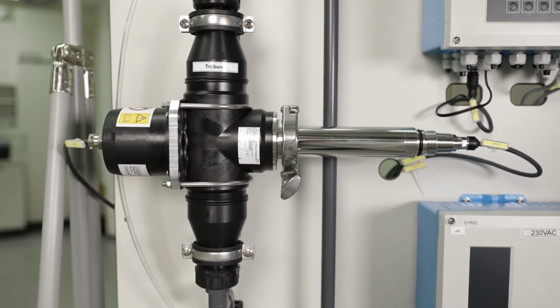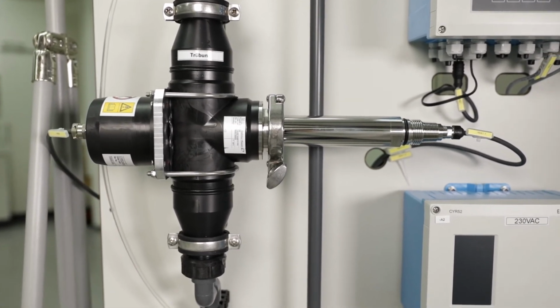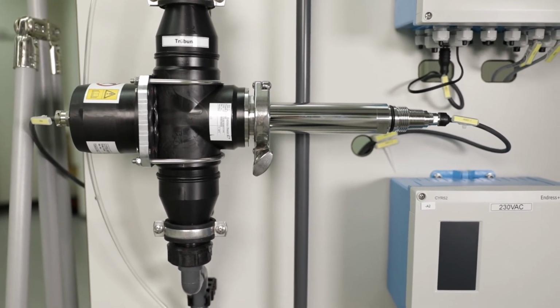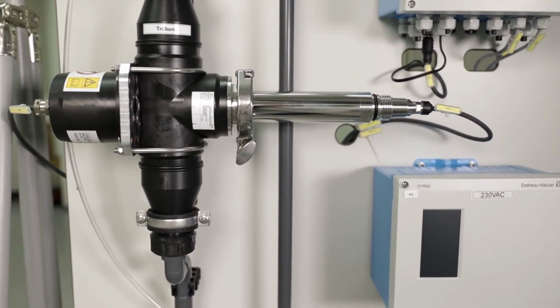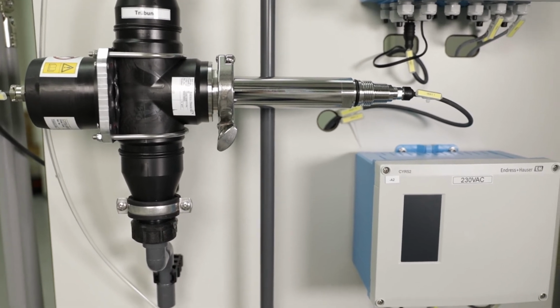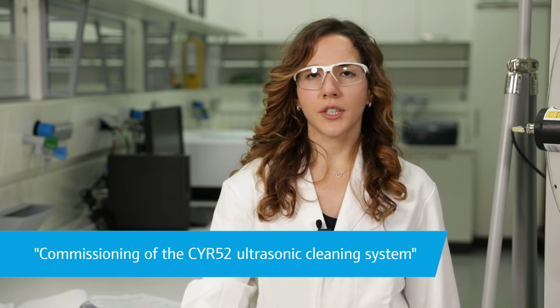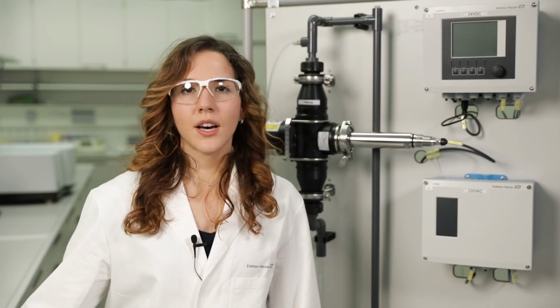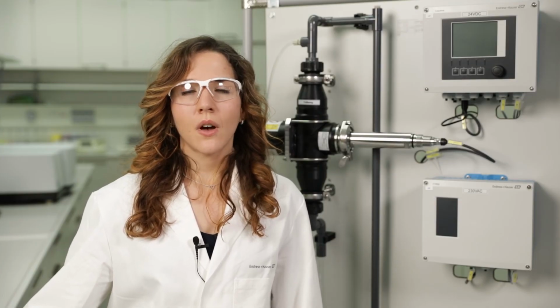For flow assemblies and pipes without the possibility of compressed air connection, there is the CYR52 ultrasonic cleaning system. The CYR52 generates cavitation in the process medium by ultrasonic waves, which dissolves dirt and air bubbles on the sensor before they are removed by the flow. To see how the cleaning unit is installed, please watch our video Commissioning of the CYR52 ultrasonic cleaning system. Regardless of which cleaning method is chosen, all of them can be controlled via the Liquiline.